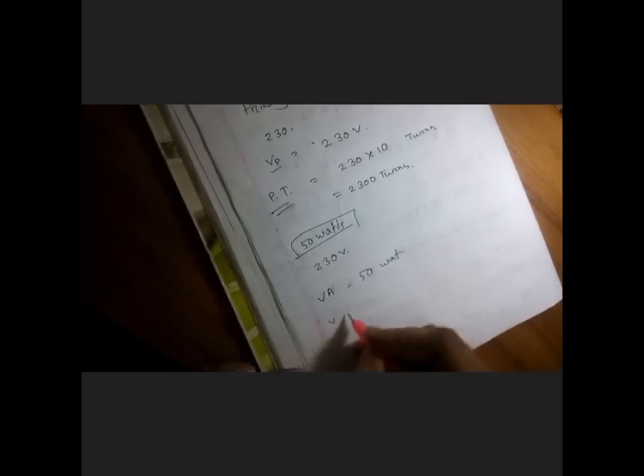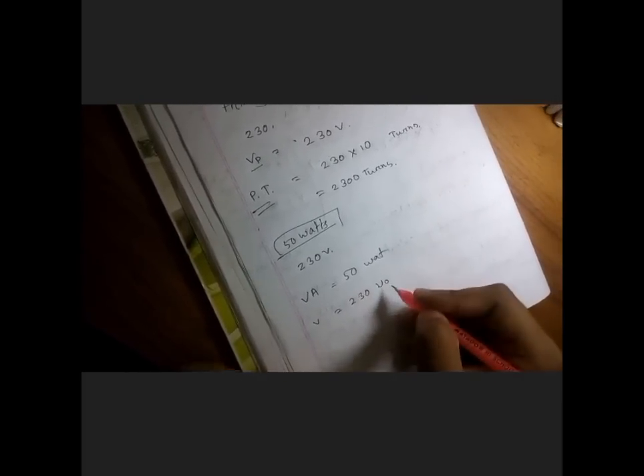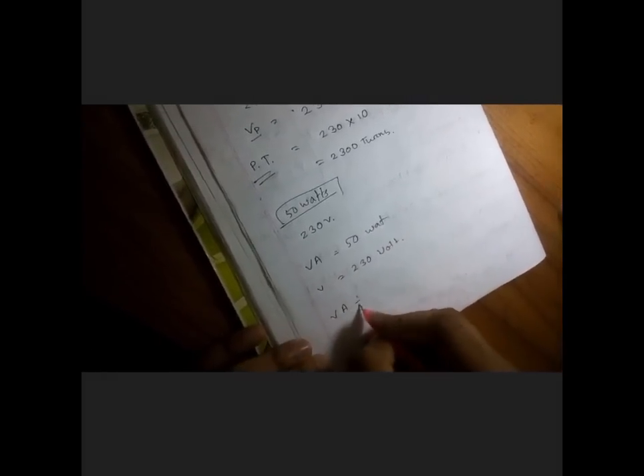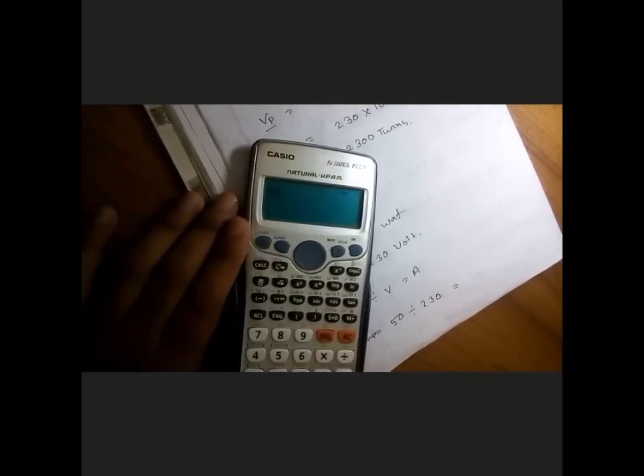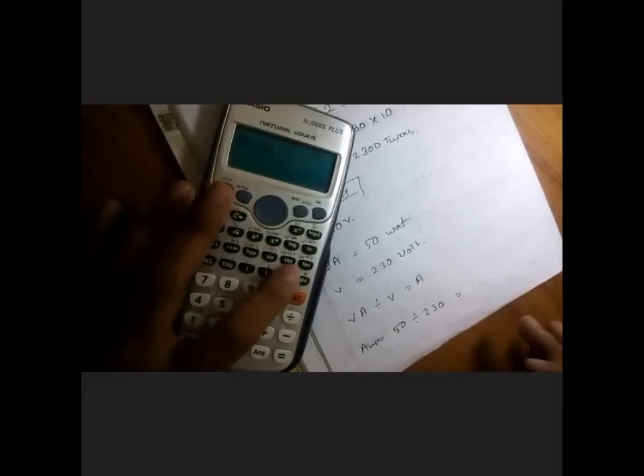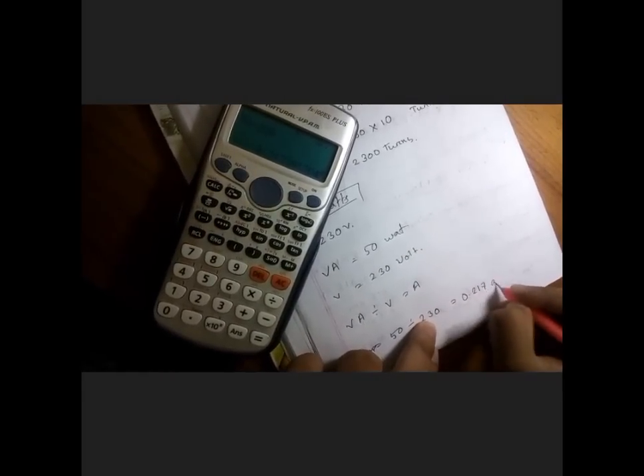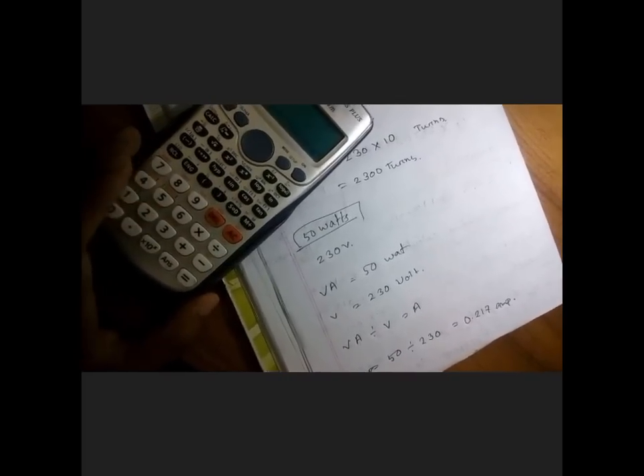And supposing that my transformer is about 50 watt. So if our primary volt is here 230 volt and VA equal to 50 watt and volt equal to 230, so if we calculate the ampere of the primary winding, it will be VA divided by V equal to A. So ampere equal to 50 divided by 230. So let's calculate 50 divided by 230 equal to 0.217 ampere. So the transformer will take 0.217 amps.